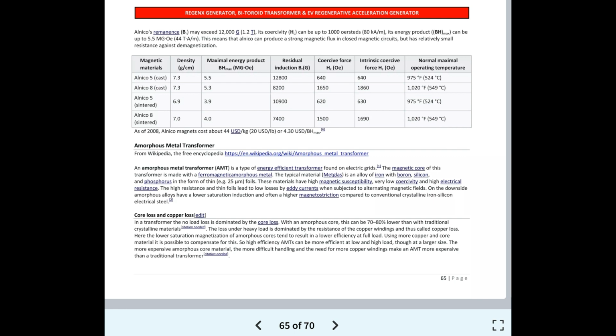Core loss and copper loss. In a transformer, the no-load loss is dominated by the core loss. With an amorphous core, this can be 70–80% lower than with traditional crystalline materials. The loss under heavy load is dominated by the resistance of the copper windings, and thus called copper loss. Here the lower saturation magnetization of amorphous cores tends to result in a lower efficiency at full load. Using more copper and core material, it is possible to compensate for this. So high-efficiency AMTs can be more efficient at low and high load, though at a larger size. The more expensive amorphous core material, the more difficult handling, and the need for more copper windings makes AMT more expensive than traditional transformer.